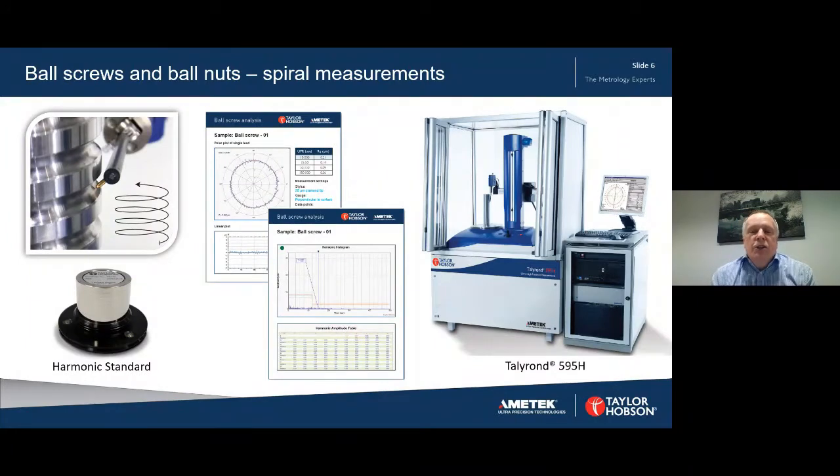The Talyrond 595H is shown there on the right. It consists of an air bearing spindle and precision datums, a column and a radial straightness unit. It also has active anti-vibration to reduce noise. The column and spindle are synchronised so that we can measure spiral measurements. Spiral measurement is shown on the left on the contact point of a ball screw, and beneath it is a harmonic standard used to confirm that we are getting good harmonic results. Typical results are shown in the middle, and we'll look at those in more detail in a few minutes.